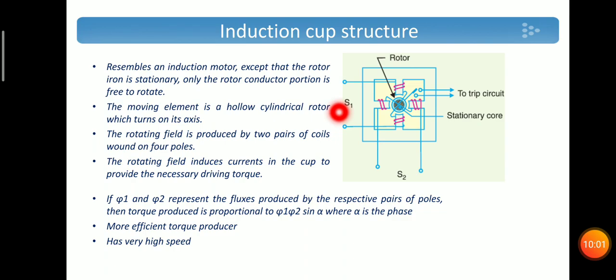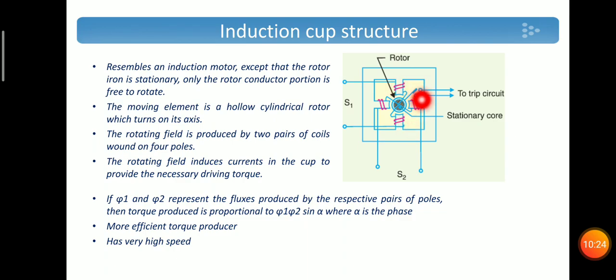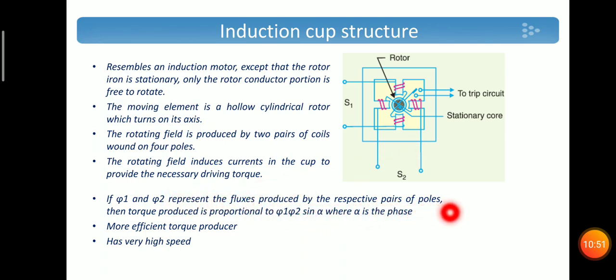The next type is the induction cup structure. It resembles an induction motor, except that the rotor iron is stationary — only the rotor conductor portion is free to rotate. The moving element is a hollow cylindrical rotor which turns on its axis. The rotating field is produced by two pairs of coils wound on four poles. The rotating field induces current in the cup to provide the necessary driving torque. Two poles carry the same flux, and the flux in the other two poles is at an angle alpha. If phi-1 and phi-2 represent the fluxes produced by the respective pair of poles, then torque = phi-1 · phi-2 · sin(α), where alpha is the phase difference. This structure has very high speed.